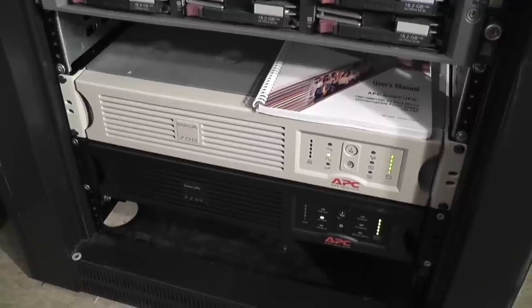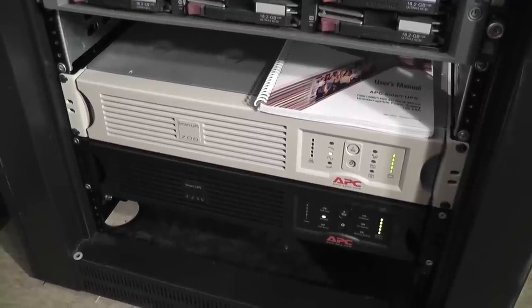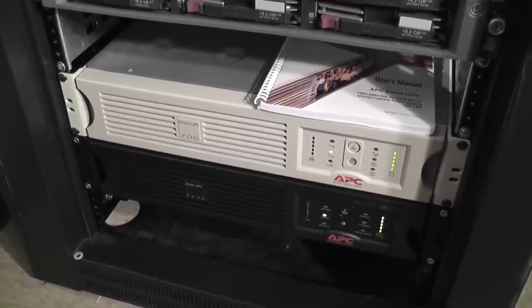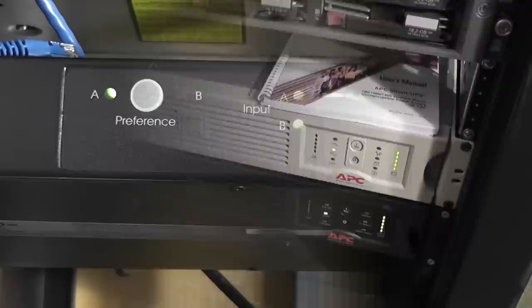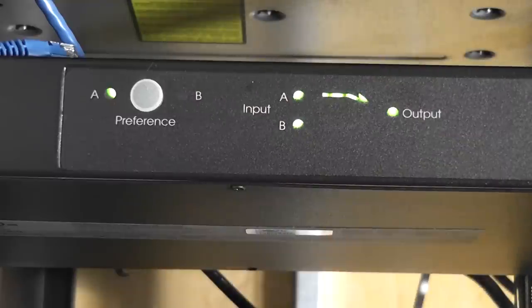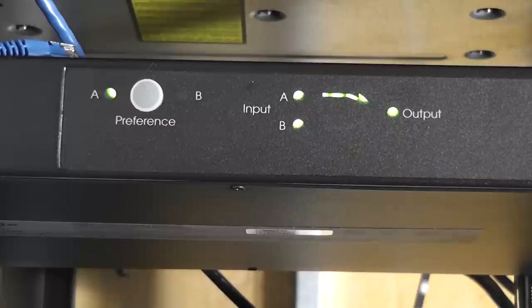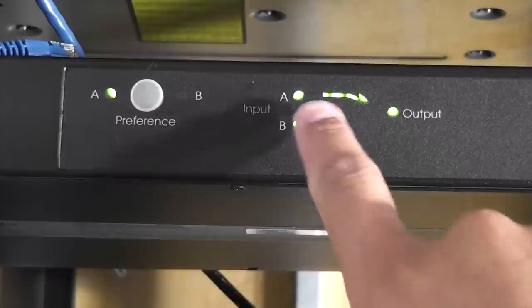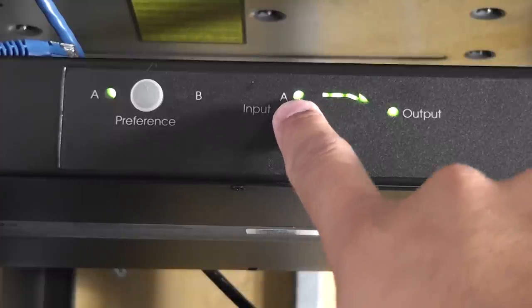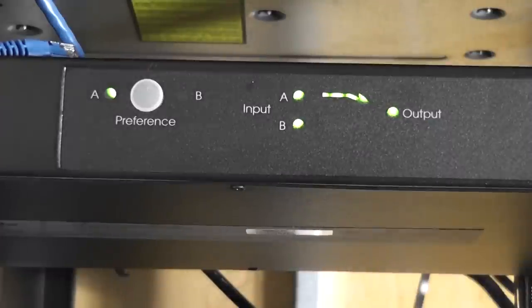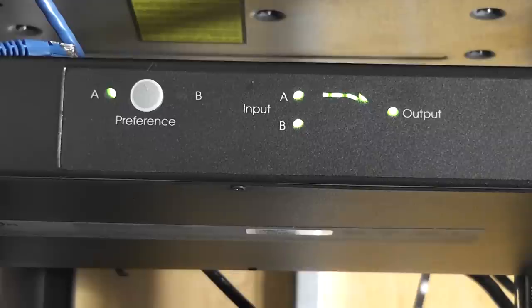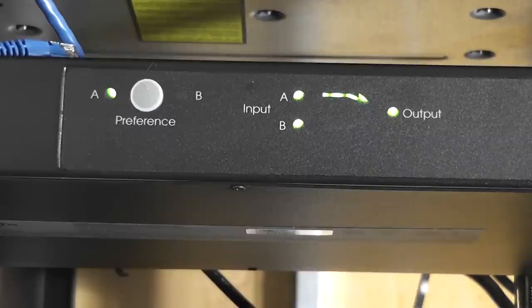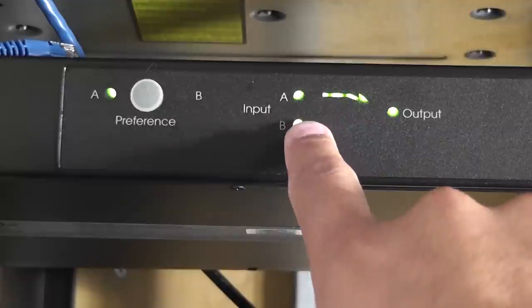Okay, camera's on a tripod and I'm zoomed in so you can actually see the status lights on the front of the unit. Right now input A, which is active, that's the Smart UPS 2200. And the test that I'm going to do is I'm going to power it down and then you should see this automatically click over and choose input B, and my equipment should not be affected. It should continue to stay on and that'll be the test.